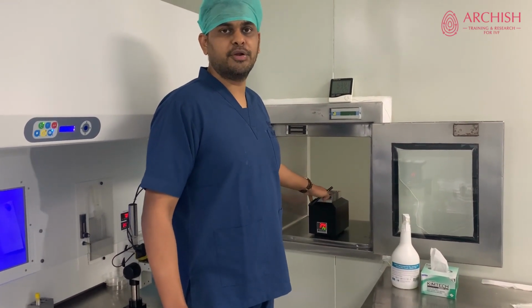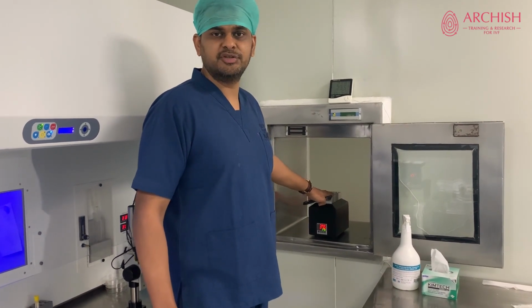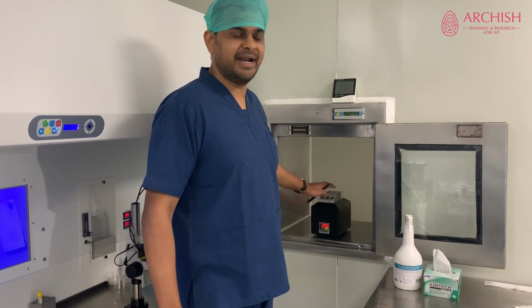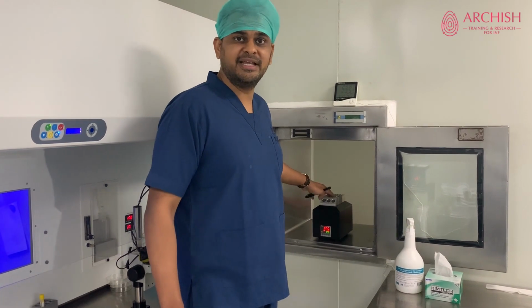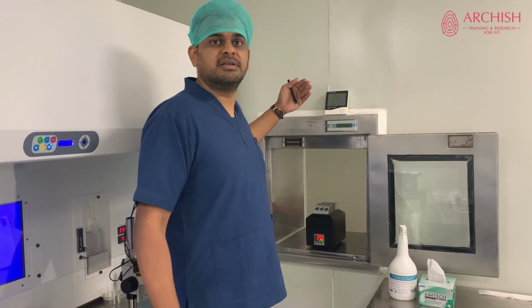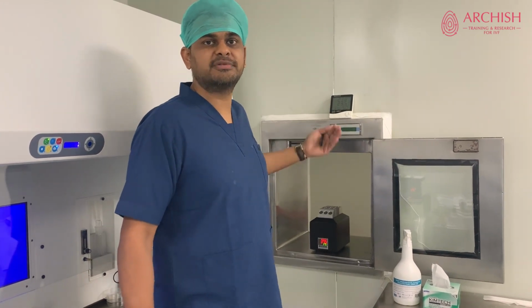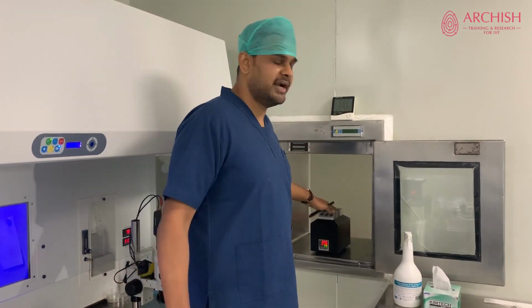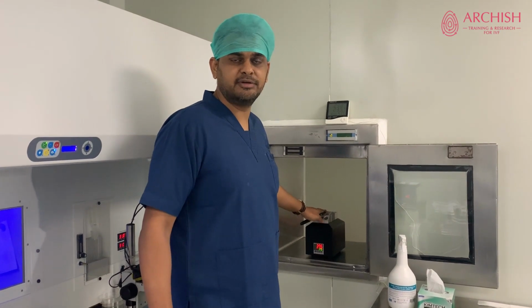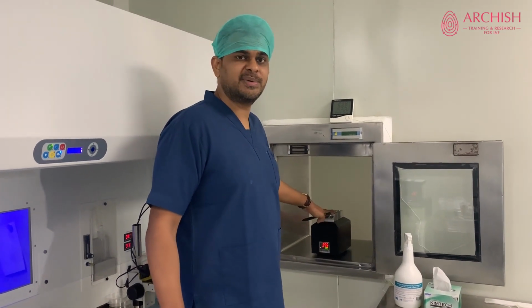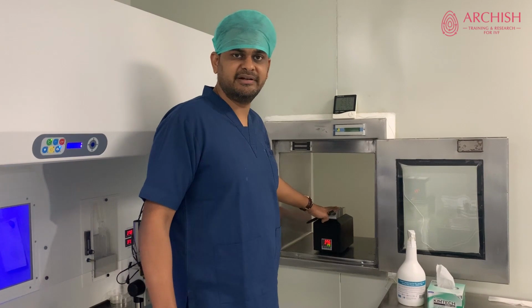During the pickups, the follicular fluid is going to be collected in test tubes, and these test tubes are going to be held inside these heating blocks till the embryologist finishes screening the current test tube containing the follicular fluid that he or she has. But until then, the pickup can't stop. So the follicular fluid containing test tubes are going to keep pouring in and are going to be held in these heating blocks. That's why it's important that the heating block is at 37 degrees.